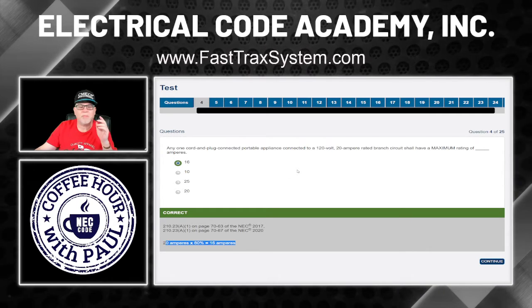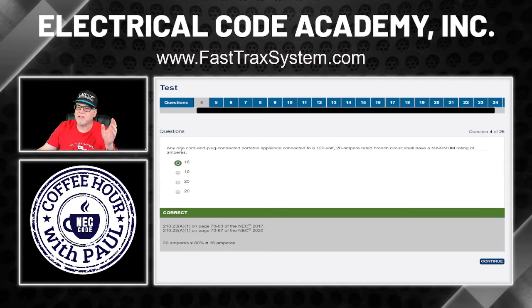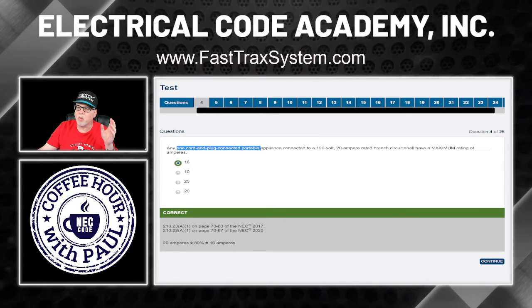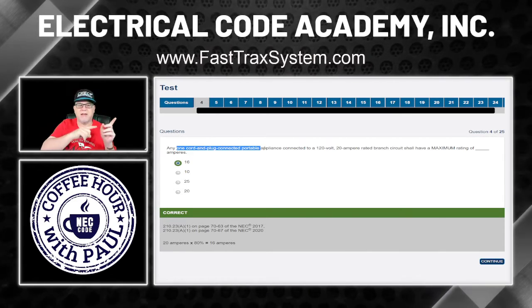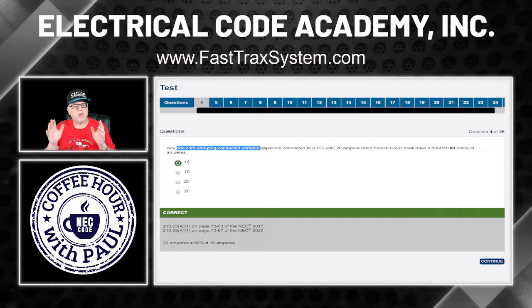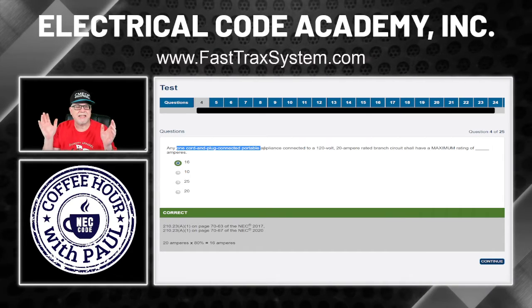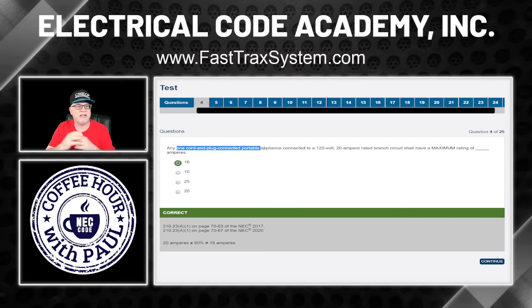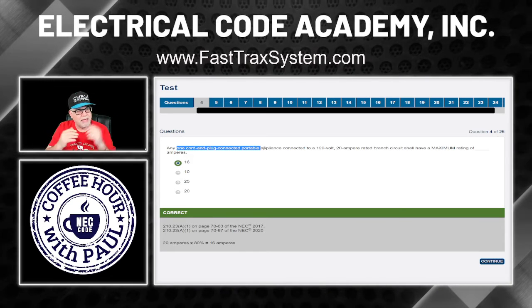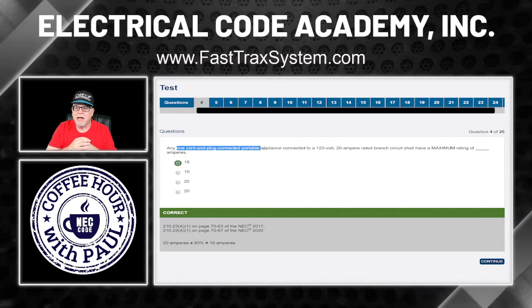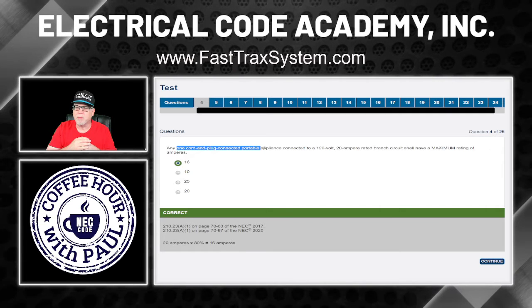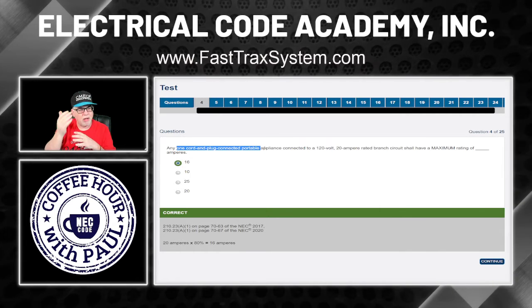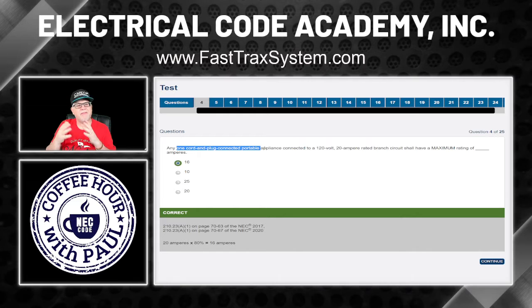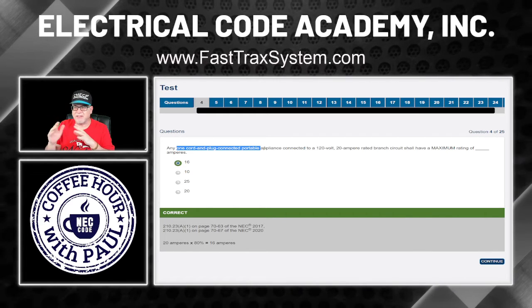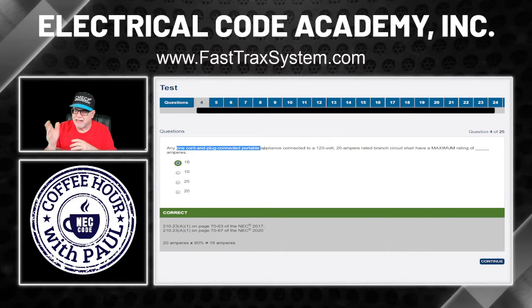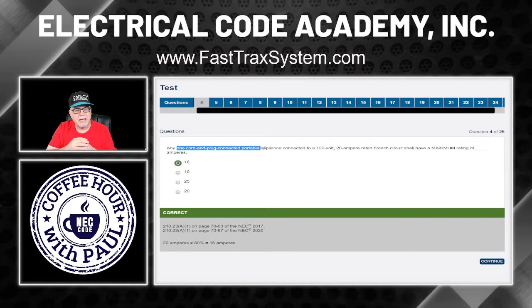Now, why did this trigger this one? Well, because it said cord and plug connected portable. So that tells me it's not fixed in place. That's not to be confused with any branch circuit typically in a house. If it's 15 amps, I can put 15 amps on it. If it's 20 amps, I can put 20 amps on it. But since this is a cord and plug connected portable appliance that's going to be plugged into that, we have this threshold we have to follow, and it's not to exceed 80%. And that's what we got in 210.23(A)(1).